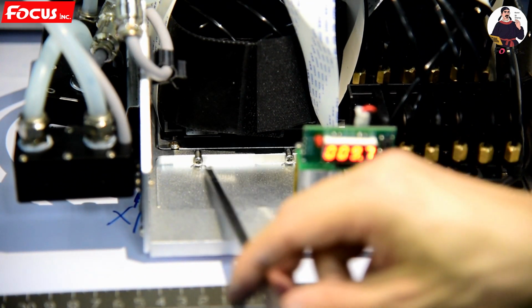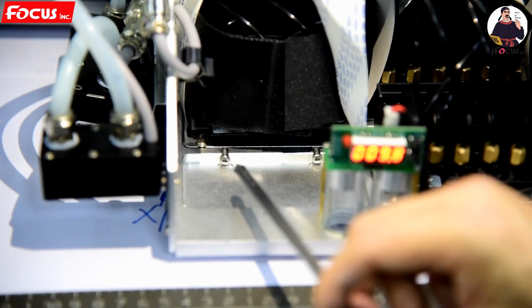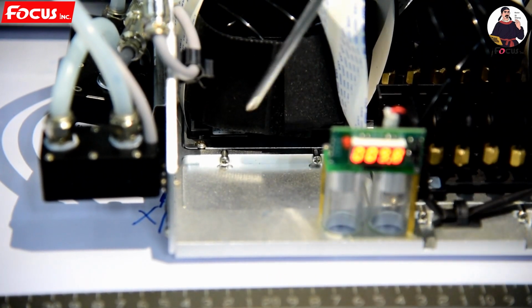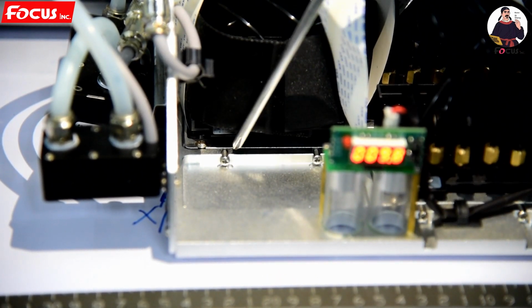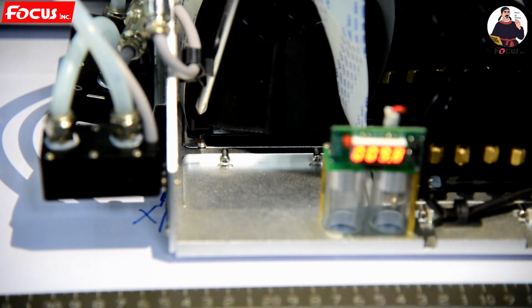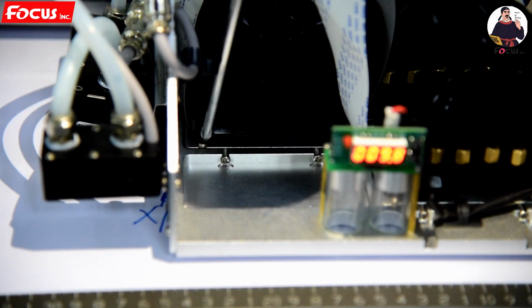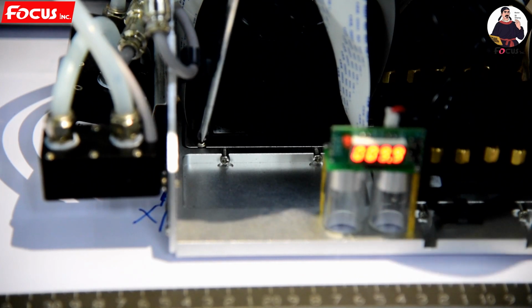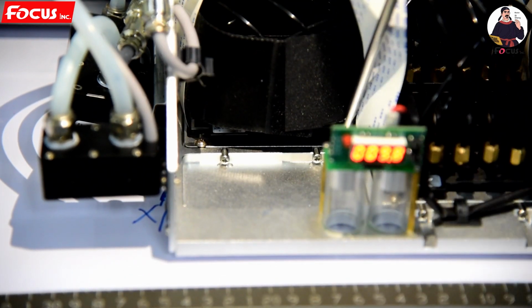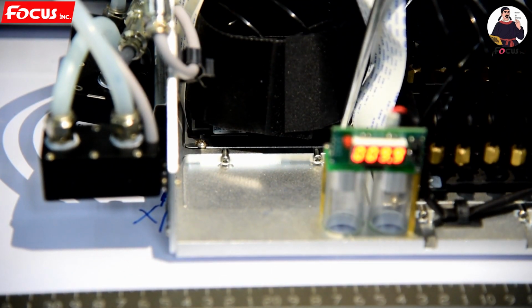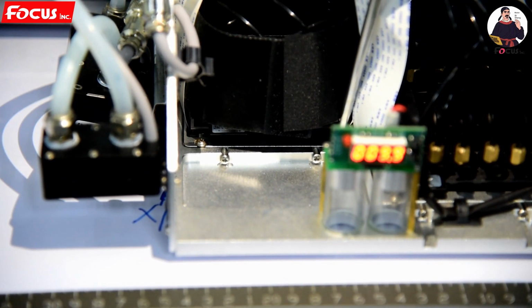1, 2, 3 for adjusting the vertical calibration. Before we adjust this screw on the print head, we need to loosen the 4 screws that lock the print head. It's not the print head we loosen, but the print head adapter board.